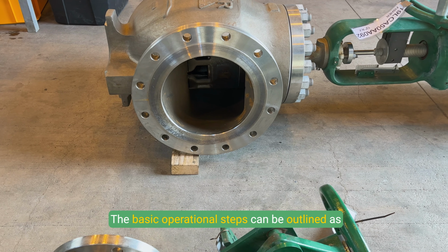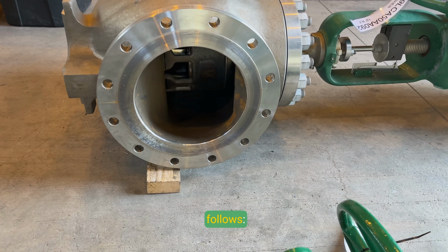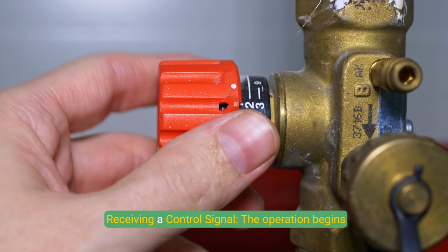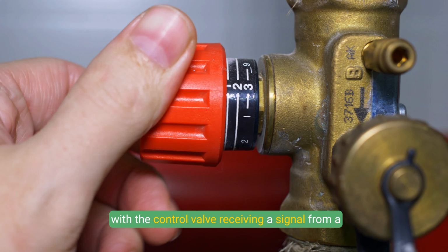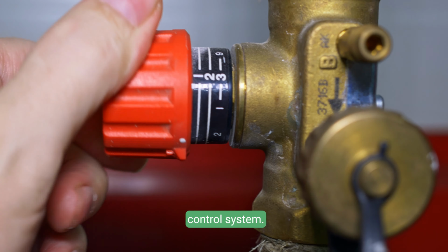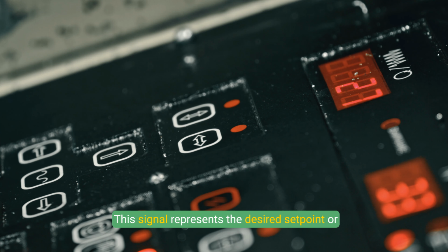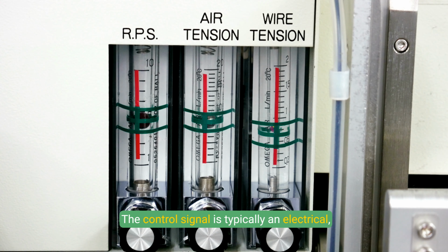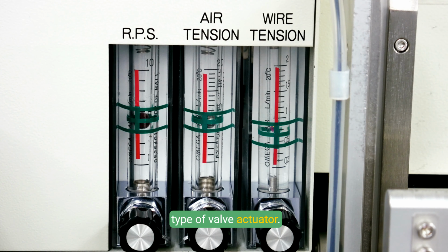The basic operational steps can be outlined as follows. Receiving a control signal. The operation begins with the control valve receiving a signal from a control system. This signal represents the desired set point or operational condition that the process should maintain. The control signal is typically an electrical, pneumatic, or hydraulic input, depending on the type of valve actuator.